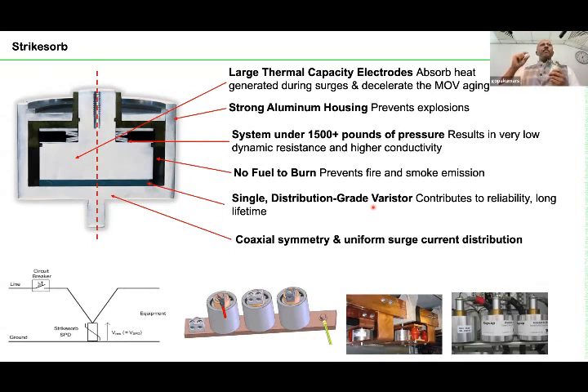It consists of a very big industrial quality metal oxide varistor. That varistor is a patented one. It's a high quality metal oxide varistor, which is mounted on this black portion, and the up and down of this MOV is pressed inside this particular aluminum can with, I think, something about 1,500 pounds of pressure.